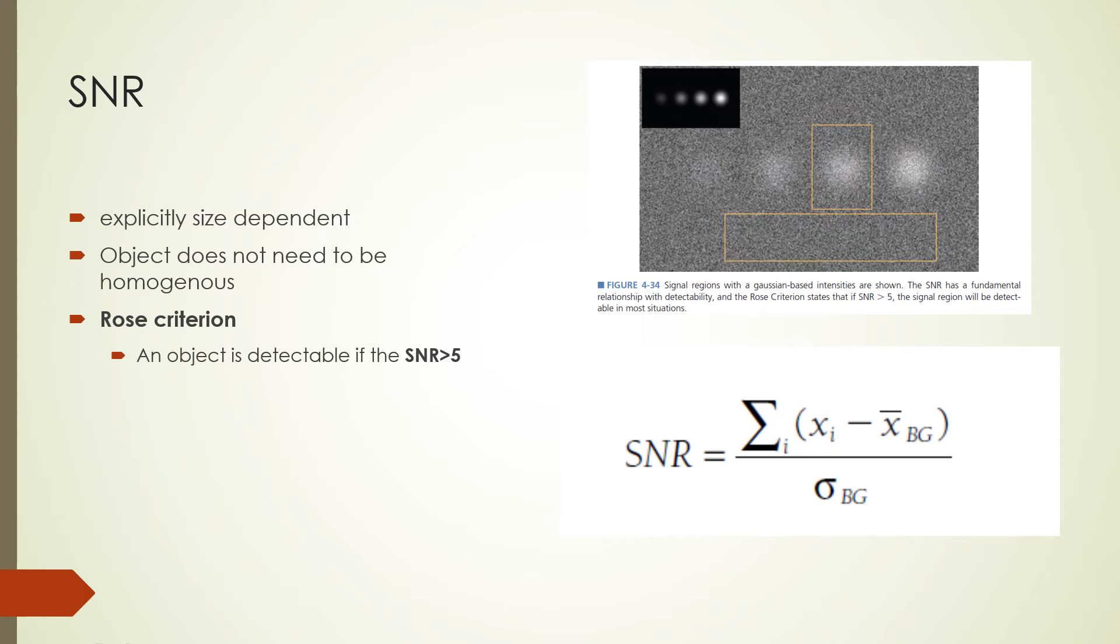Signal to noise ratio is a metric similar to the contrast to noise ratio. However, unlike contrast to noise ratio, signal to noise ratio is explicitly size dependent and the size and shape of the object are part of the calculation. Also, the object itself does not need to be homogeneous, but the background must be homogeneous. The formula on this slide shows that signal to noise ratio is a difference between the mean background signal and the signal at each pixel i in the image. This is then divided by the standard deviation of the background. Signal to noise ratio is one of the most meaningful metrics that describes how well an object will be seen by the typical observer. It was shown that if the signal to noise ratio is greater than 5, then an object will almost always be detected. This is called the Rose criterion.